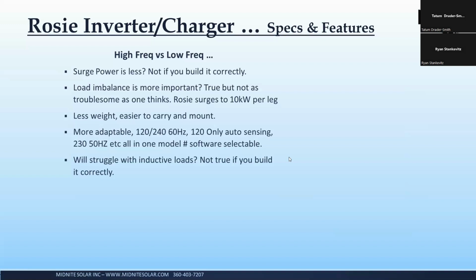And we do have a question on how long it will surge at 10 kilowatts. So this is an interesting, fun thing to look at and play with. If you're bored and you really want to sit down with a beer and do some research, every inverter manufacturer talks about surge time and surge numbers, and they're all different. So in a nutshell, when you go through UL, through any NRTL, nationally recognized testing laboratory, the current UL 1741 says that you can do unlimited up to, I believe, 5 minutes.